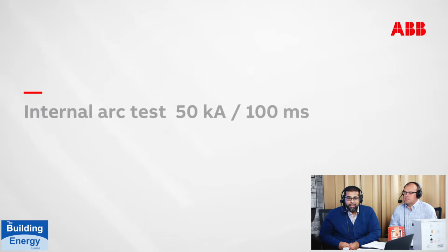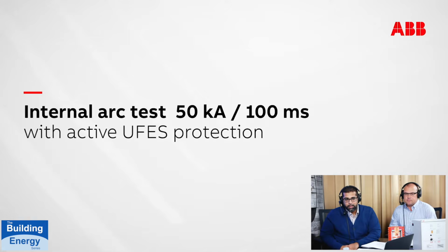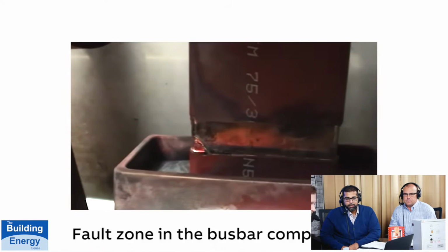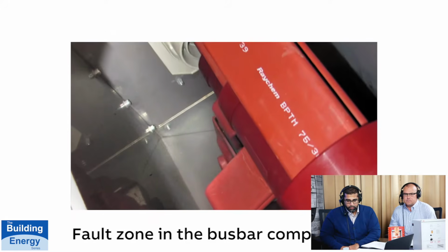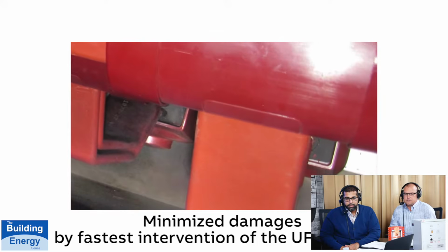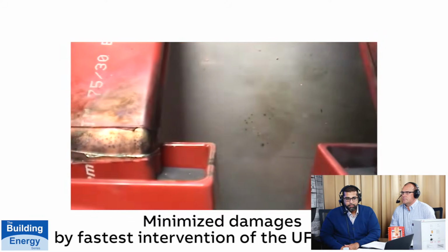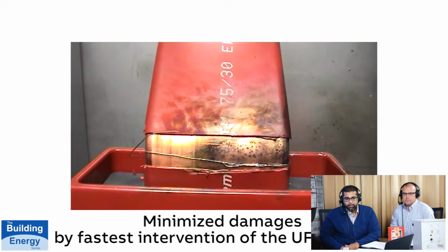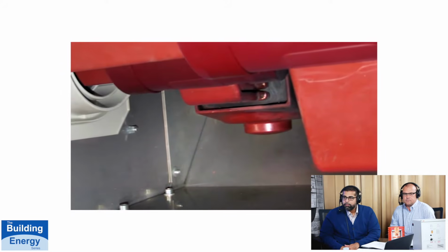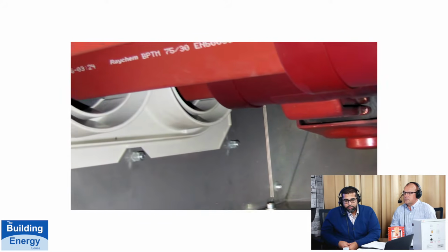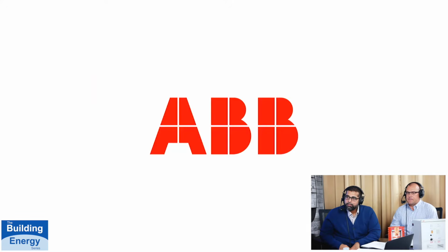And then this is a test with the UFES installed, where it will actuate in less than 4 milliseconds. You see the difference in the damage done with the UFES and without the UFES that you saw previously. You see it's a minimal amount of damage. You still see some carbon buildup, but it requires maybe some minor refurbishment. And a lot of this depends on how severe the fault is. This is the worst case we're simulating here, a three-phase fault. But you can see with the UFES device, you've actually saved your switchgear.